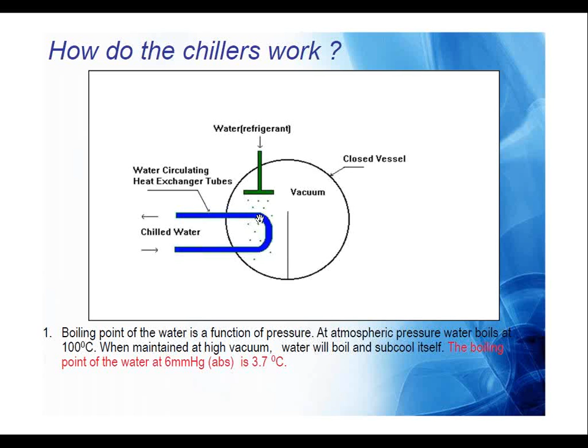Now this evaporated refrigerant vapor will go towards the absorber. In the absorber, again there will be concentrated lithium bromide, which is nothing but the absorbent. The concentration level of this lithium bromide will be close to 64%. There is a strong affinity between lithium bromide and the water vapor, that is the refrigerant. Lithium bromide is in the same category of the halogen family as NaCl, and there is always a strong affinity for lithium bromide as well as NaCl towards the water vapor.